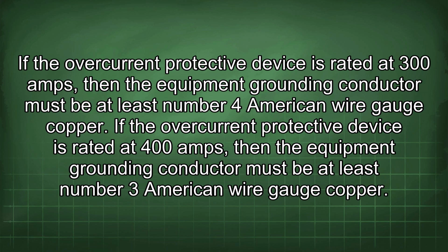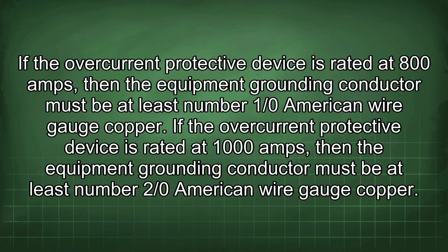If the overcurrent protective device is rated at 400 amps, then the equipment grounding conductor must be at least number 3 American wire gauge copper. If the overcurrent protective device is rated at 500 amps, then the equipment grounding conductor must be at least number 2 American wire gauge copper. If the overcurrent protective device is rated at 600 amps, then the equipment grounding conductor must be at least number 1 American wire gauge copper. If the overcurrent protective device is rated at 800 amps, then the equipment grounding conductor must be at least number 1/0 American wire gauge copper.